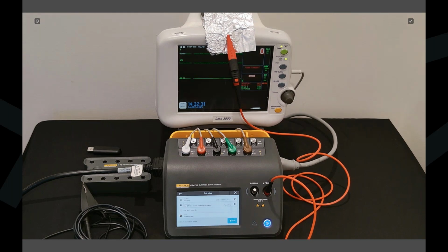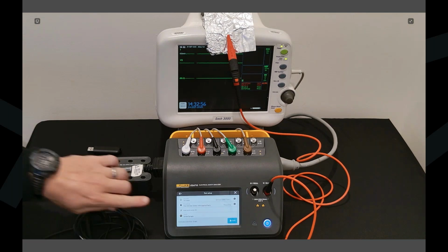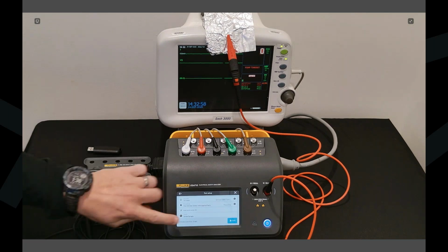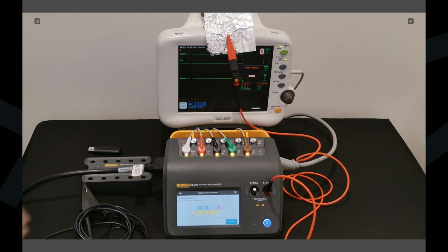Incoming inspections, electrical safety, inspections out on the floor. We talked about if you added a device and you were doing an incoming inspection, you could capture all that information on your instrument. Then you could run a quick electrical safety test, so you've done a full incoming inspection on the floor. No need for your laptop, no need for anything else. But again, here's our standard boilerplate. Let's run through this electrical safety pretty fast, to show you the power of OneQA and how fast we can get through a lot of it.